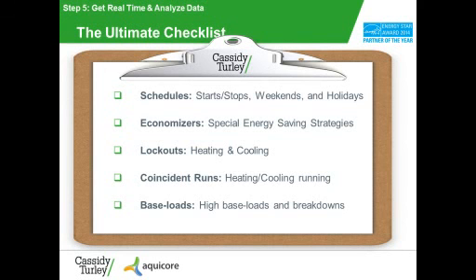So we talked a little bit about schedules, start and stop times, and there are two things to really think about when it comes to start and stop times. Start times should never look the same in July and August and January, February as they do in September and October and in the spring. We see swings of start times range probably in the 2-hour, sometimes pushing 3-hour difference.